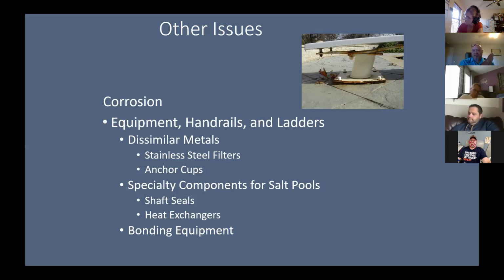Remember I talked about water's conductive, but it's not conductive enough. That's why we add salt. So now what I've done is I've increased the conductivity of the water itself. When we go down to that last bullet point there in bonding equipment, if the pool's not properly bonded, anything that's electrical in contact with the water, albeit a salt system is low voltage DC, there's a tendency for that electricity to radiate out into the pool, trying to find a way to discharge.